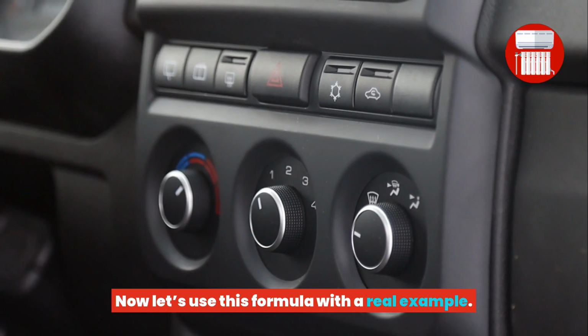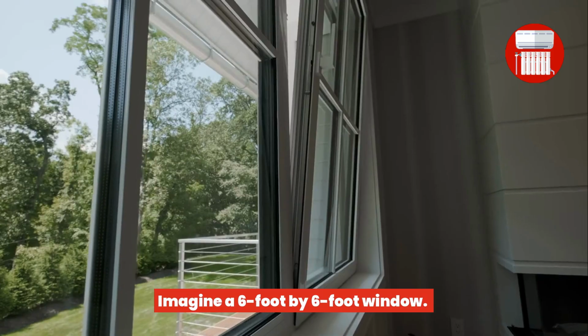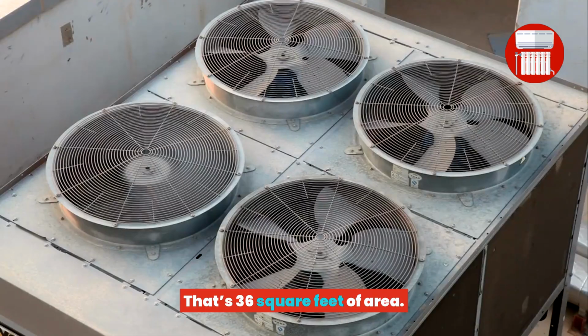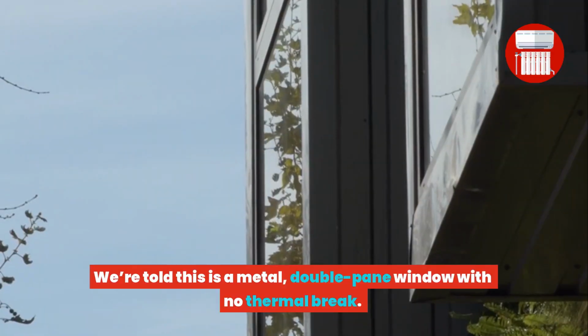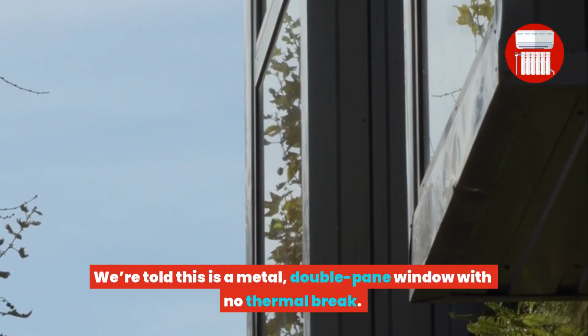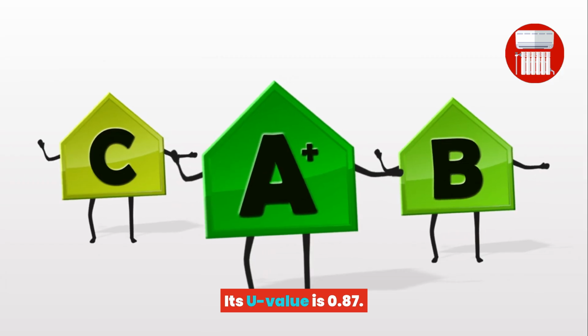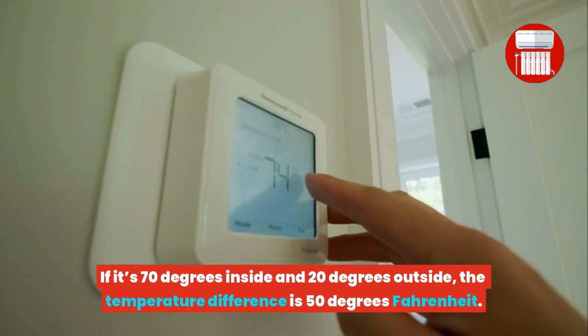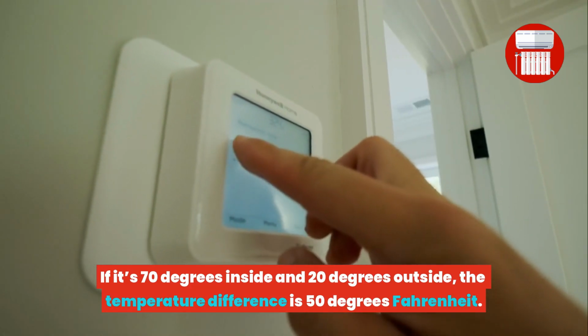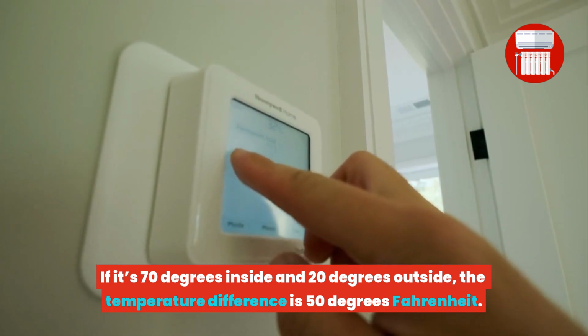Now let's use this formula with a real example. Imagine a 6-foot by 6-foot window. That's 36 square feet of area. We're told this is a metal double-pane window with no thermal break. Its U value is 0.87. If it's 70 degrees inside and 20 degrees outside, the temperature difference is 50 degrees Fahrenheit.